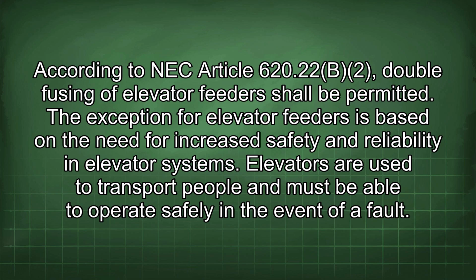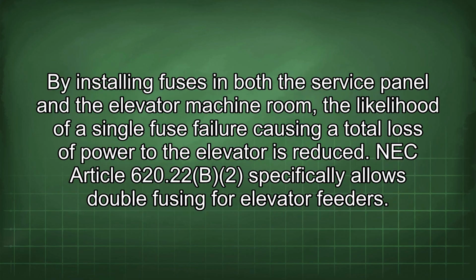The exception for elevator feeders is based on the need for increased safety and reliability in elevator systems. Elevators are used to transport people and must be able to operate safely in the event of a fault. By installing fuses in both the service panel and the elevator machine room, the likelihood of a single fuse failure causing a total loss of power to the elevator is reduced.